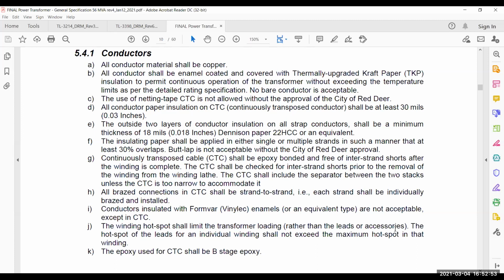So now, in the next transformer, we're going to do this in the specification. We're going to put in the clause: all conductor paper insulation CTC shall be at least 30 mils. So when we procure the next transformer and do the design review, we'll force the manufacturer: look, we put in our specification that you have to put in this minimum insulation for our conductor. You just can't go aggressive in the design.